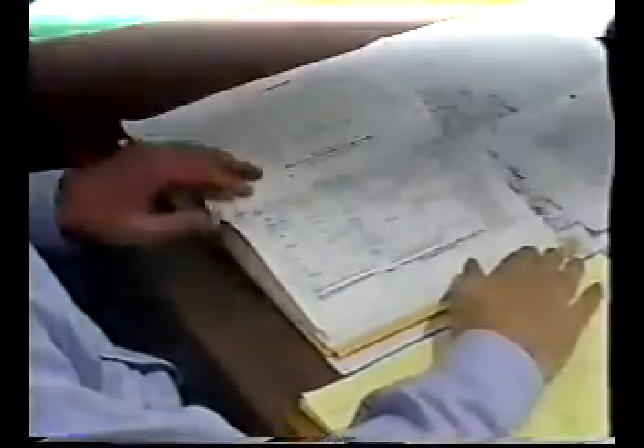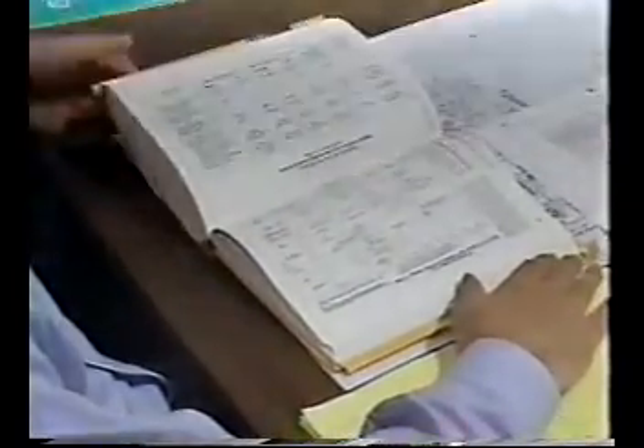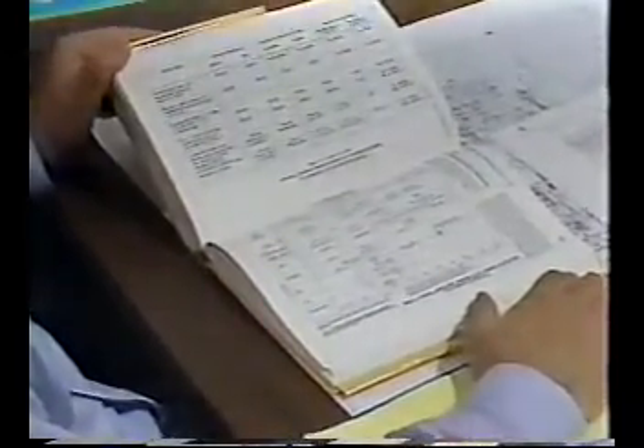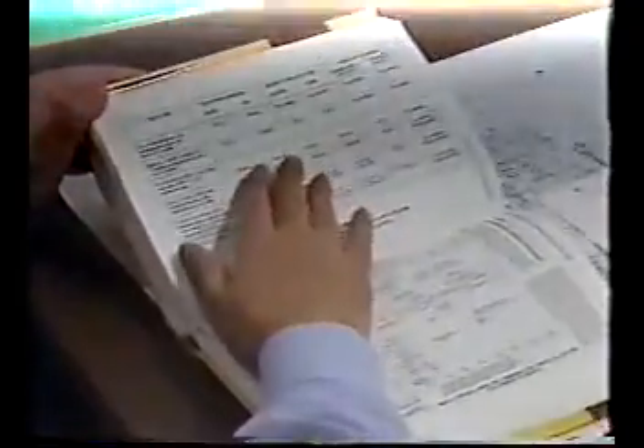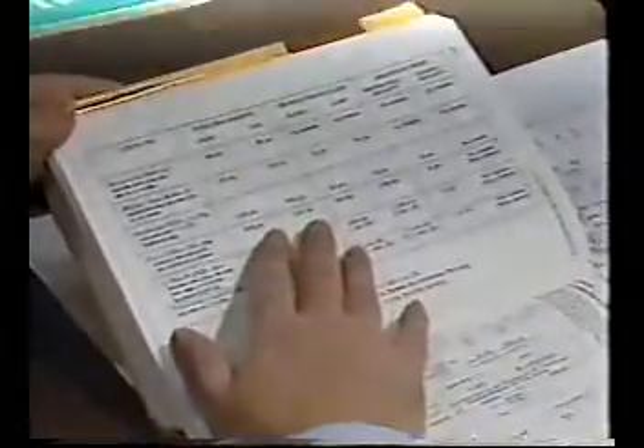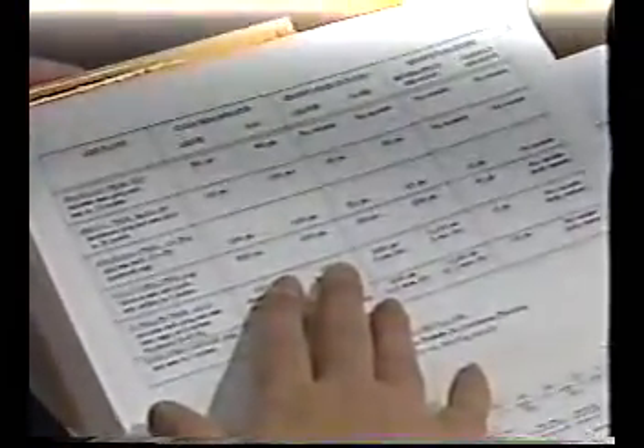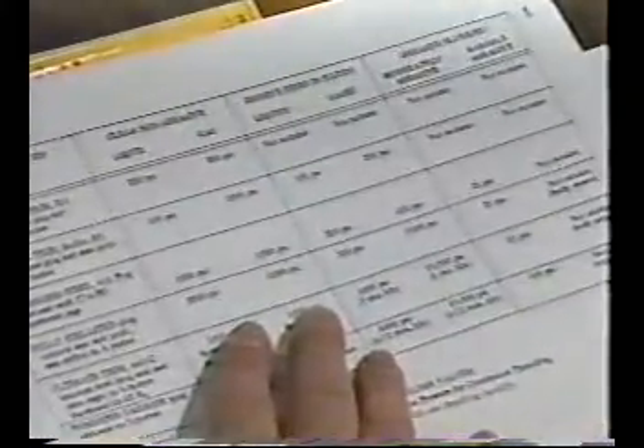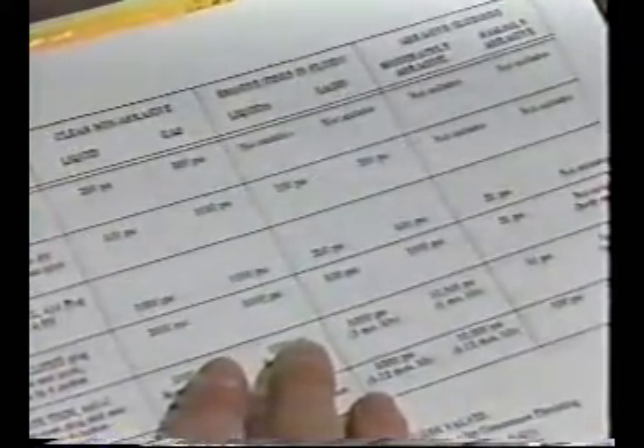With all the data gathered and organized, a preliminary valve selection can be made. Unfortunately, there is no formula that can be used to identify the ideal control valve for any application. Instead, a list of potentially suitable control valves must undergo a process of elimination, where unsuitable valves are rejected.